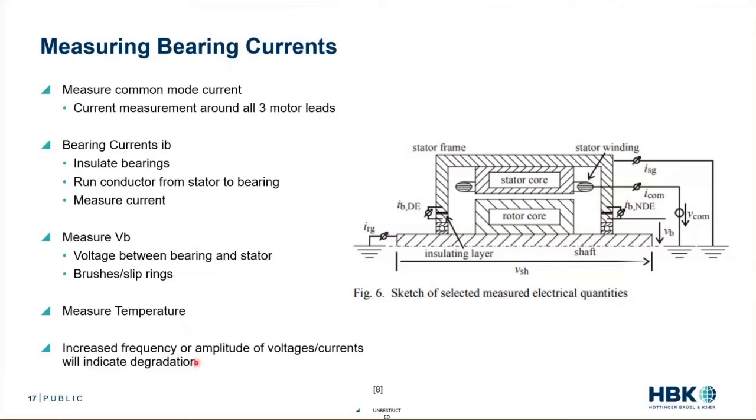And we can look at increases in frequency of discharge or increases in amplitude of discharge in parallel with increased temperatures, and identify that degradation over time and really see how that bearing behaves, how my total efficiency behaves. We can understand this whole system.